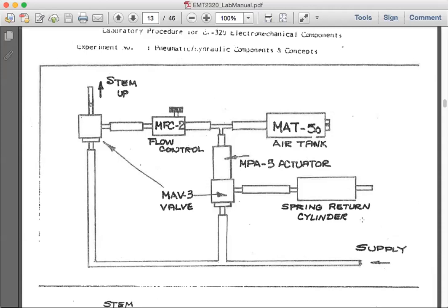When the piston returns, is it slowly returning as the chamber depressurizes, or once it depressurizes, does it go back in? It returns as the left chamber depressurizes, because there is no longer pressure coming from the bottom of the three-way valve. When you depressurize the top of the system, the actuator goes up, then the stem goes up, so the pressure stops at the bottom of this three-way valve.